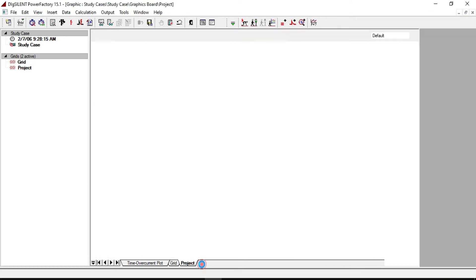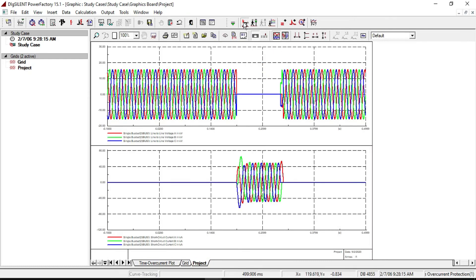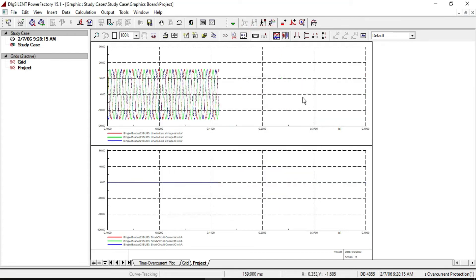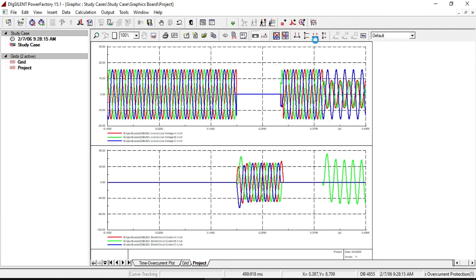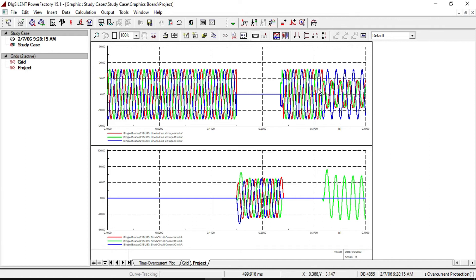Let's check it. Now you can see that after 0.4 seconds there is a fault on phase B. The phase B voltage has collapsed and the phase B short circuit current has risen up.